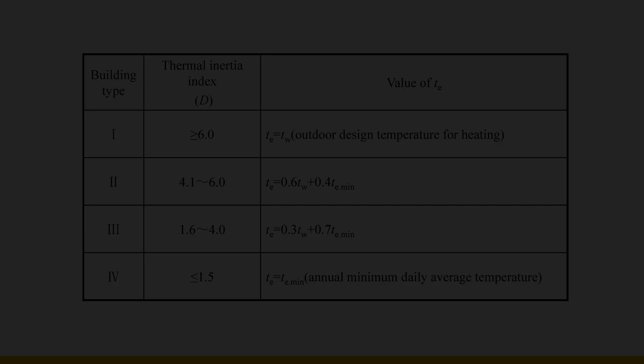The thermal inertia index is divided into 4 ranges, and the thermal inertia index decreases in turn, respectively for Type 1, Type 2, Type 3, and Type 4 buildings, of which Type 1 and Type 2 buildings are heavy buildings, and Type 3 and 4 buildings are light buildings. The calculated outdoor temperature of different building types at the same location is different. The calculated outdoor temperature of Type 1 building is equal to the calculated outdoor temperature of heating, which is equivalent to the average daily temperature that has 5 days per year without being guaranteed to meet the target.